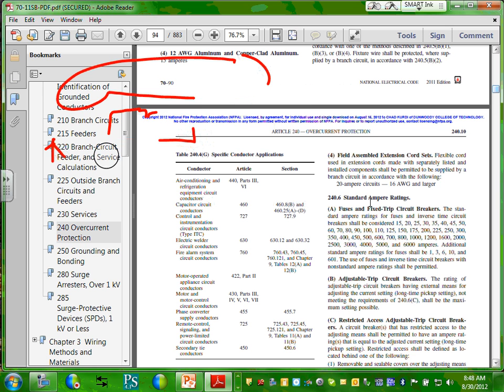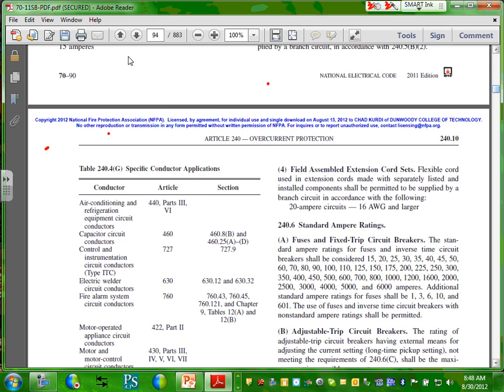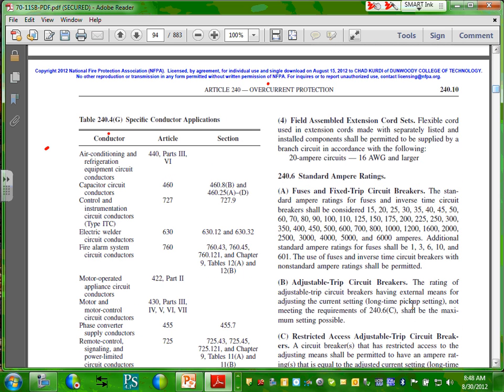Okay, so let me just erase these quick here and go to 240.6. Just for one time only, from now on when we go to commercial, I'm going to be asking you to go to 240.6 and you say, Chad, we're there. One time I show it to you. So 240.6, these are standard overcurrent protection devices. Here's what we use in the US. Typically, you're going to be from the 15 amps all the way to 4,000 amps. That's what we typically use, though it allows you to go to 6,000 amps.